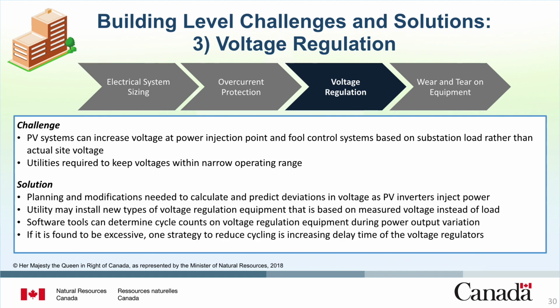To mitigate these challenges, planning and modifications are needed to calculate and predict deviations in voltage at various locations on the distribution system as PV inverters inject power at their locations. Also, at the substation, the utility will study the need to install new types of voltage regulation equipment that is based on measured voltage rather than load. The intermittent operation of the renewable energy generator may cause increased cycling on the new or existing voltage regulation equipment. Various software tools that model power flow can determine cycle counts on voltage regulation equipment during changes in variable generation power output. If found to be excessive, one strategy to reduce cycling is increasing the delay time of the voltage regulators.